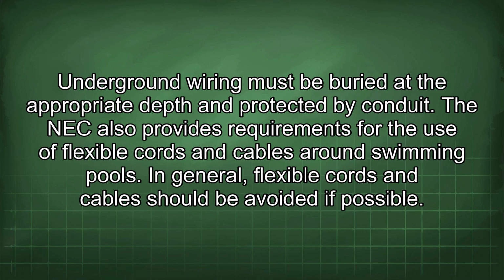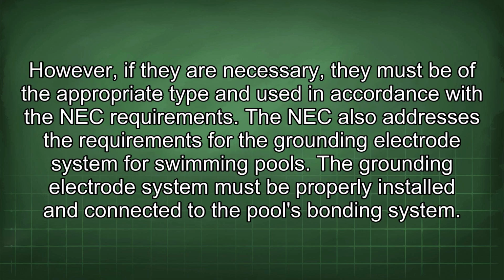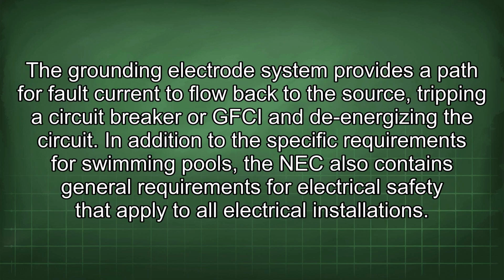The NEC also provides requirements for the use of flexible cords and cables around swimming pools. In general, flexible cords and cables should be avoided if possible. However, if they are necessary, they must be of the appropriate type and used in accordance with the NEC requirements. The NEC also addresses the requirements for the grounding electrode system for swimming pools. The grounding electrode system must be properly installed and connected to the pool's bonding system. The grounding electrode system provides a path for fault current to flow back to the source, tripping a circuit breaker or GFCI and de-energizing the circuit.